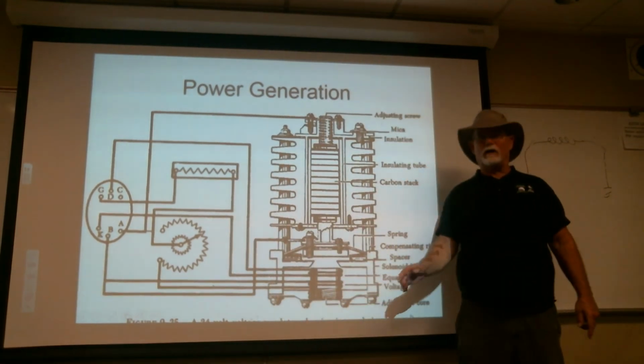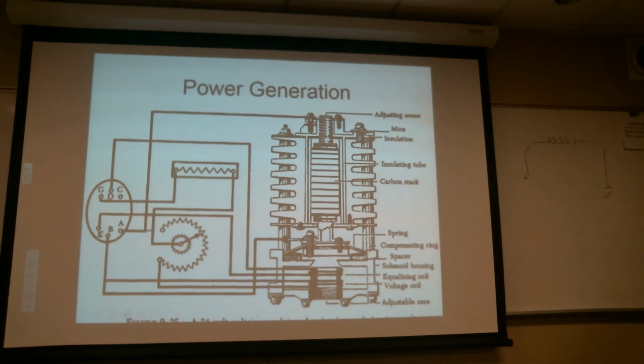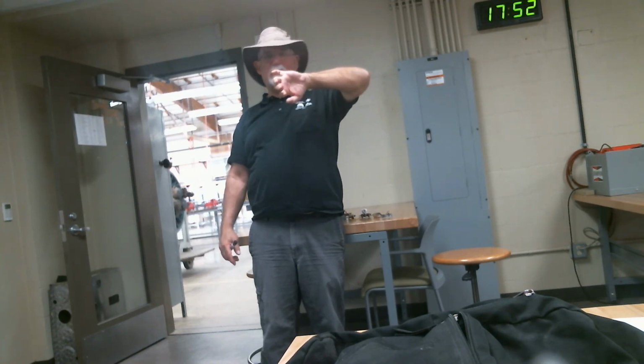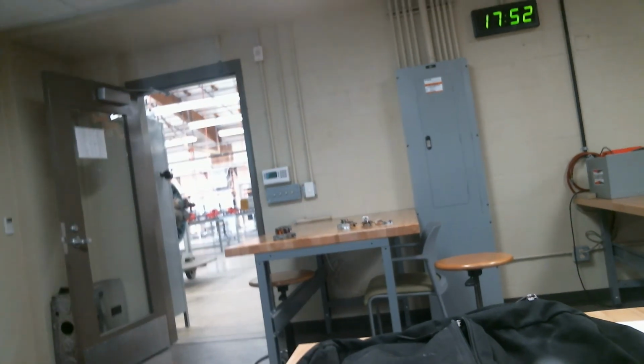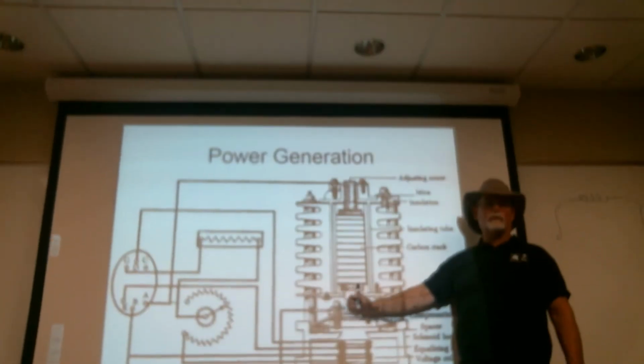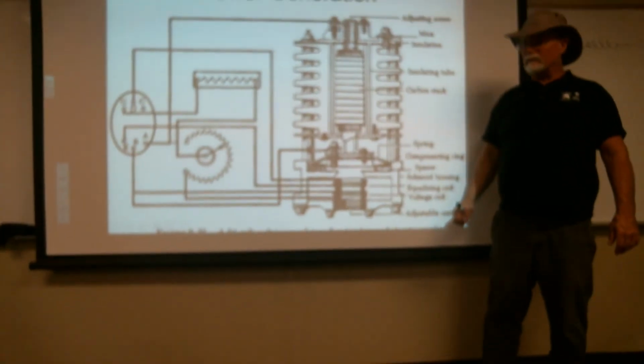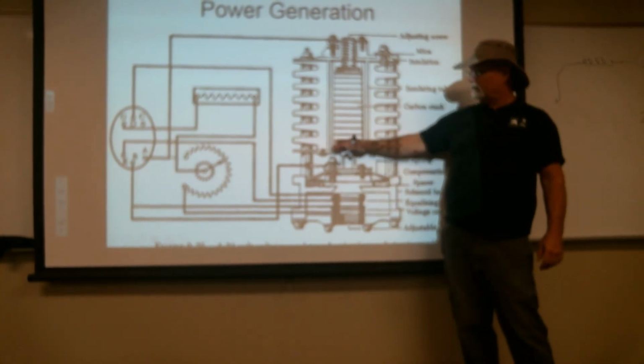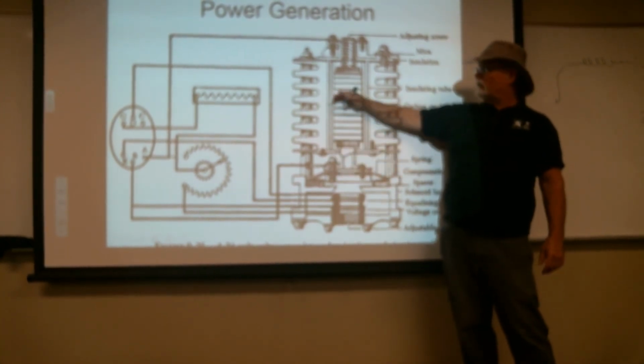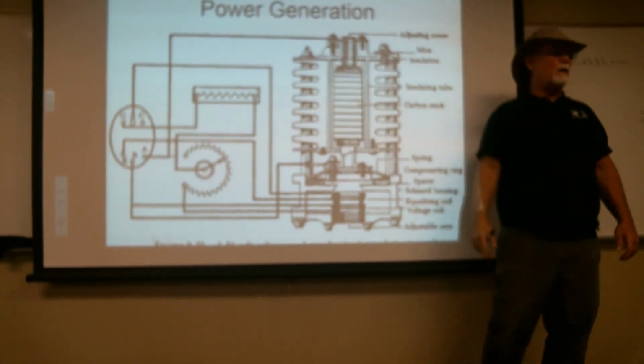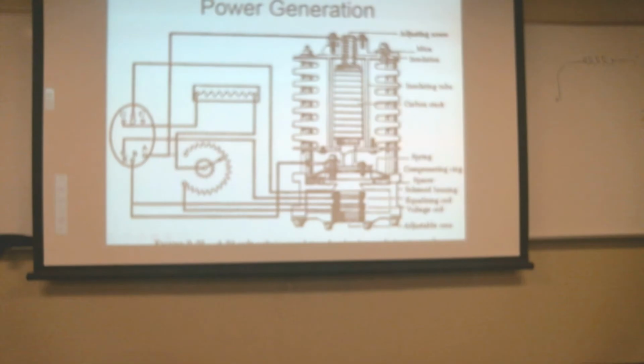That voltage sensing coil has to follow the left-hand coil rule. In terms of polarity, it's got to keep the North Pole. If I send the current the other way, the magnetism works the opposite direction, and instead of pulling back when voltage goes up, it pushes the spring, causing the voltage to go even higher. What I want is: voltage goes high, this pulls the carbon pile back, resistance goes up, current to the field goes down. So I can't switch that voltage sensing coil.